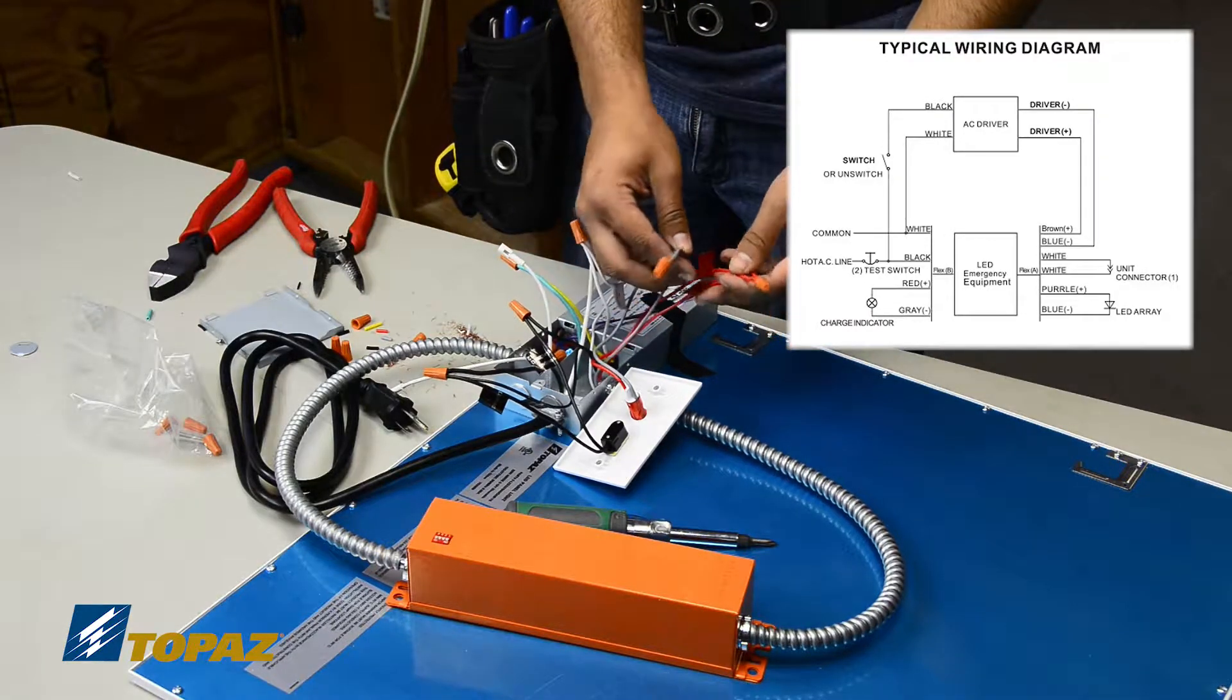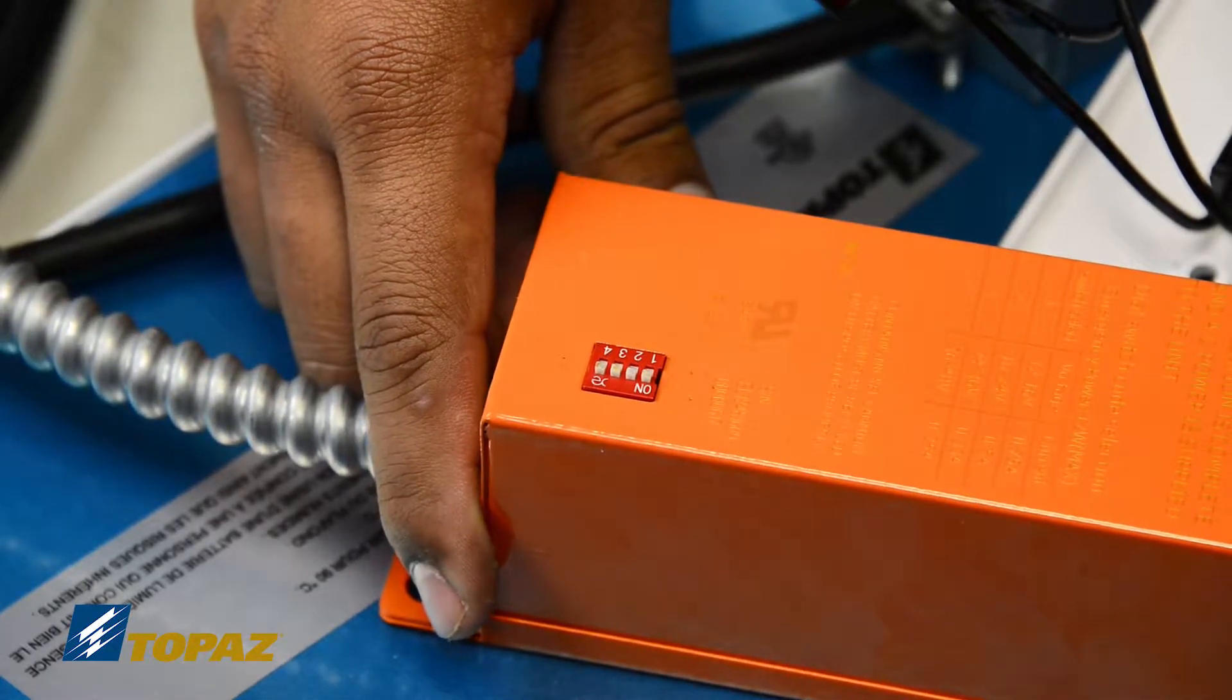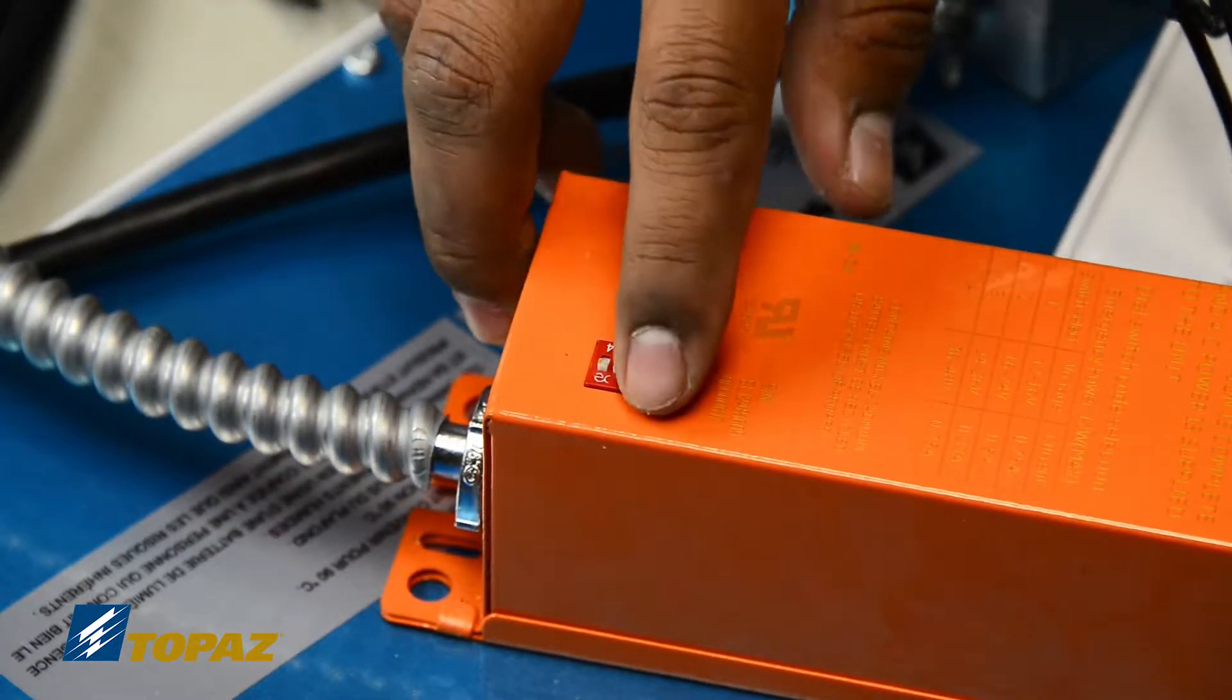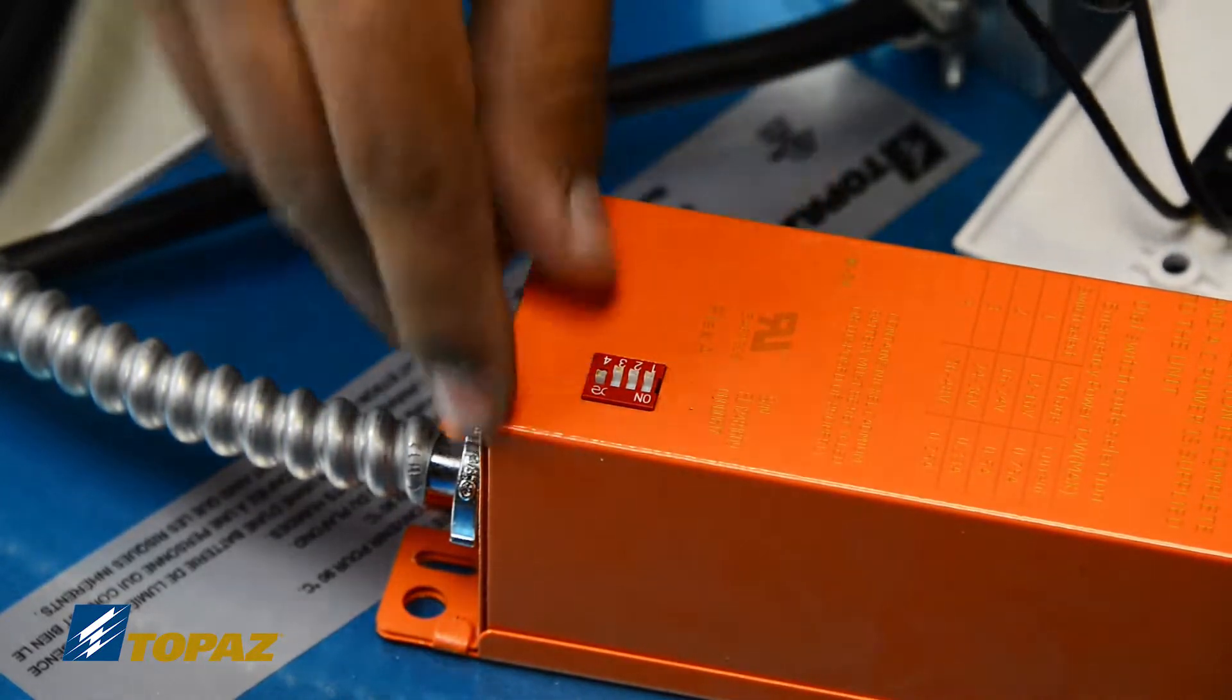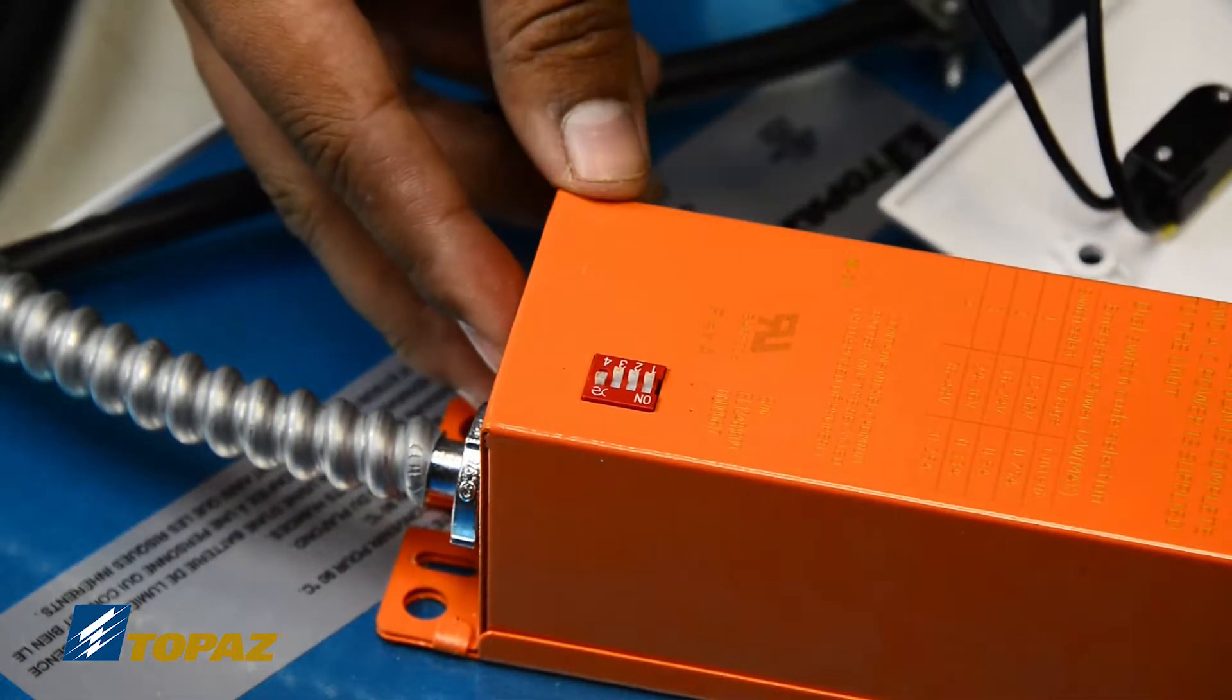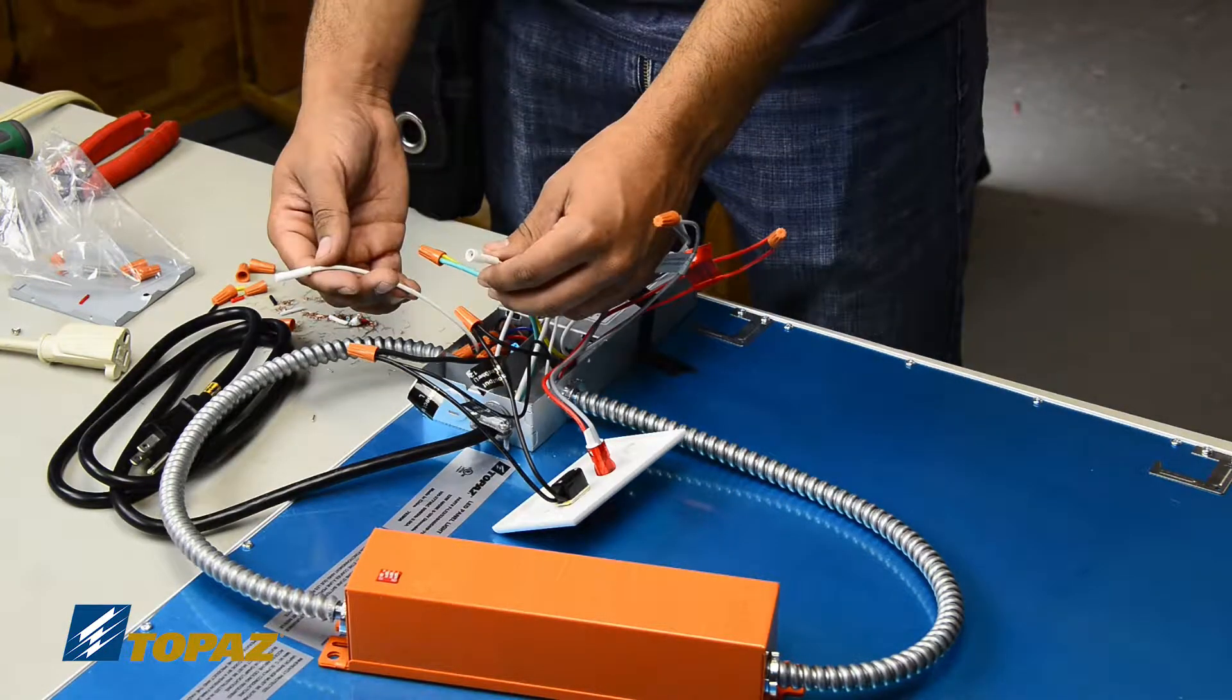The emergency ballast comes with the dip switches set in the on position. What we need you to do is to only keep the number four dip switch in the on position. Number one, number two, and number three slide down to the off position. What that is doing is regulating the voltage to 40 volts. This emergency ballast needs to be supported according to national electrical code.